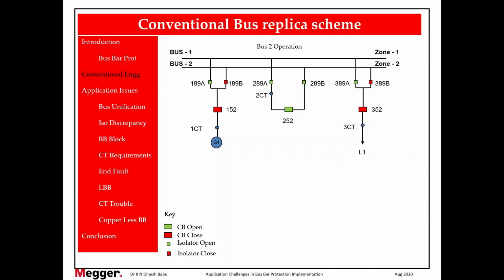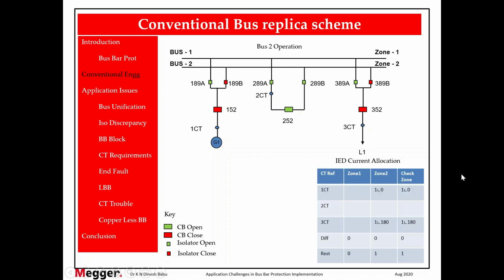Now we are feeding through zone 2. Incoming, the bus coupler is open, feeding through 3 CT, going out. Now this is the current allocation and this is the direction. There is no change in direction of incoming current and outgoing current. And it is read in zone 2 because 189B and 389B are closed, A is open. Now what are the differential and restrained currents? 1 angle 0 plus 1 angle 180, this is 0. Restrained current is the maximum current. So your system is perfect in this example.